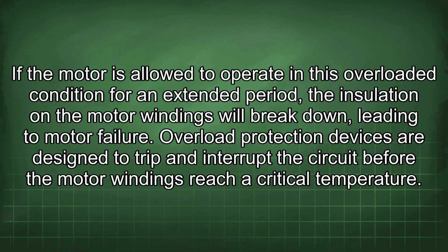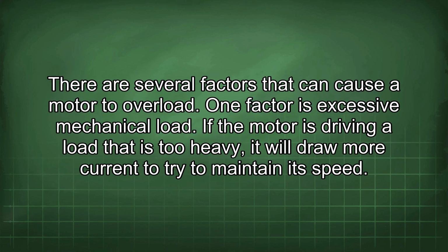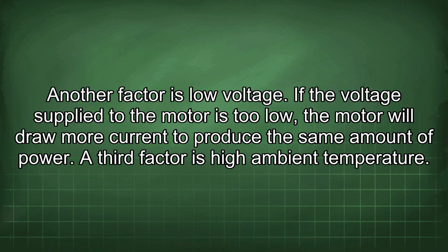Overload protection devices are designed to trip and interrupt the circuit before the motor windings reach a critical temperature. There are several factors that can cause a motor to overload. One factor is excessive mechanical load. If the motor is driving a load that is too heavy, it will draw more current to try to maintain its speed. Another factor is low voltage.